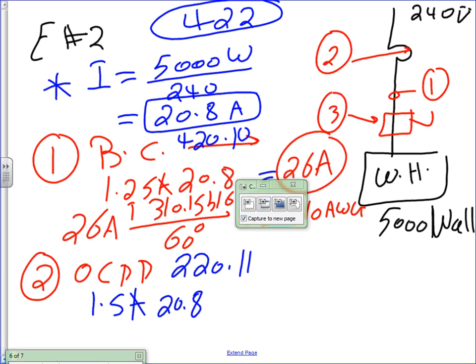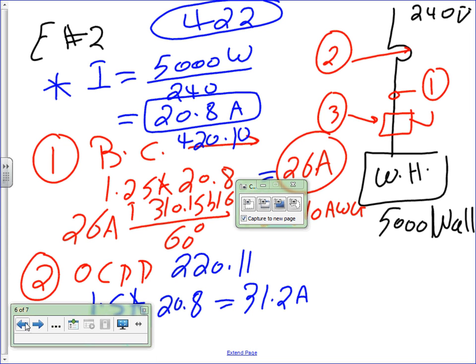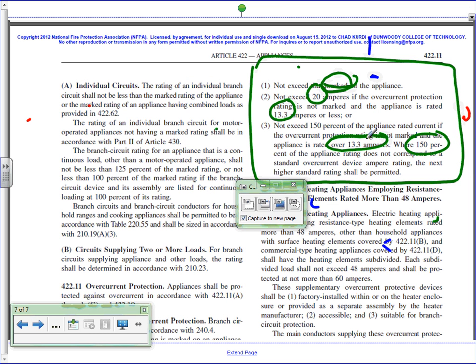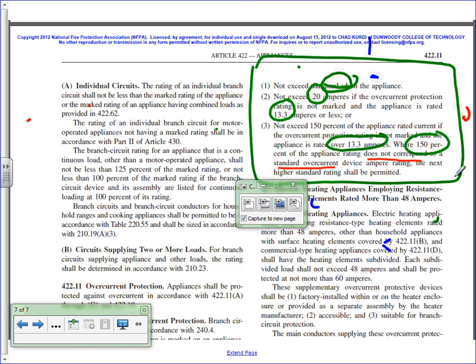20.8. I need two gentlemen to agree on an answer. 1.5 or 1.15? 1.5, 150%. 31.2. 31.2 amps. Okay. Now, let me just see. I think it tells you guys here. You guys write. It says where the 150 does not correspond to a standard overcurrent protection device.